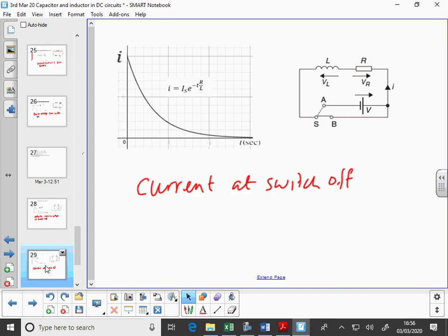The other thing that can happen is this high induced EMF, if you've got electronic sensors on a machine connected to the coil of a relay, when you break it, that induced EMF can send a current back up the line and zap sensitive electronic equipment. So what they do is they put a diode in that will allow that current to dissipate in a circle around the coil instead of going back up the line. So there are implications to what happens.